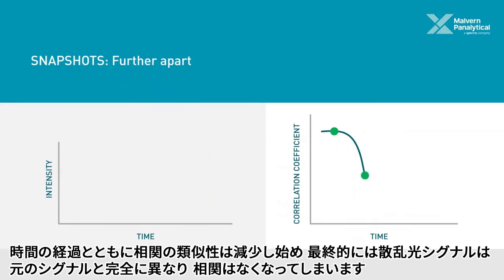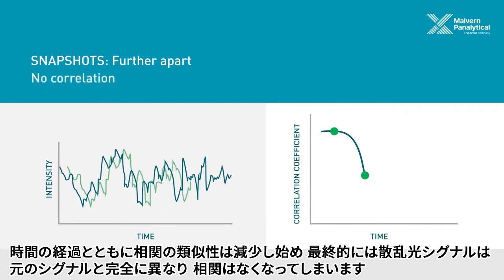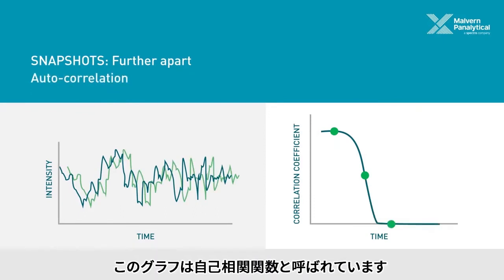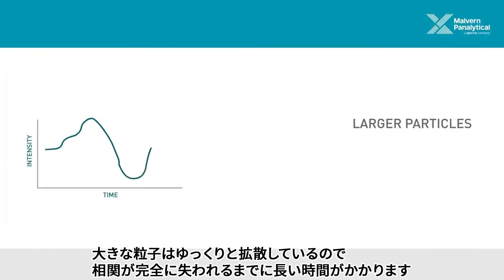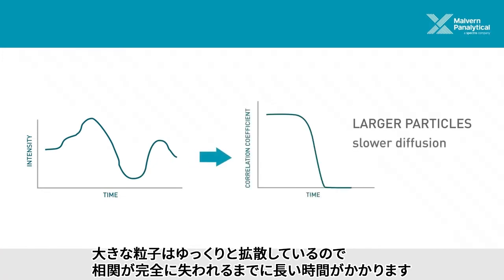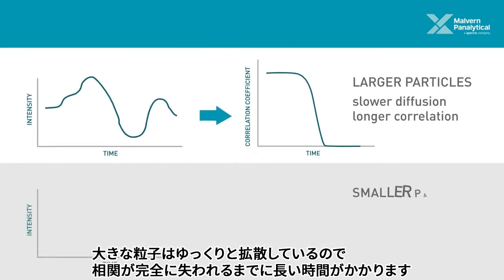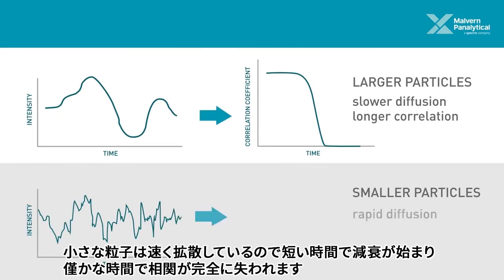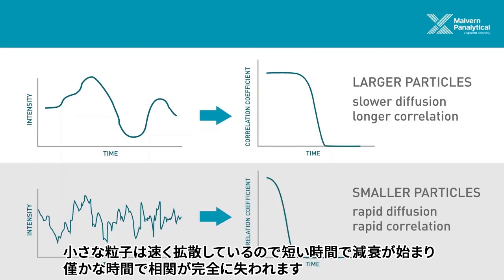Eventually the intensity signal changes completely, and there is no longer any correlation with the original signal. This process is called auto-correlation. The larger the particles being measured, the more slowly they diffuse, and the longer it takes for a complete loss of the correlation signal. For small particles, which undergo rapid diffusion, the correlation of the signal will decay rapidly.